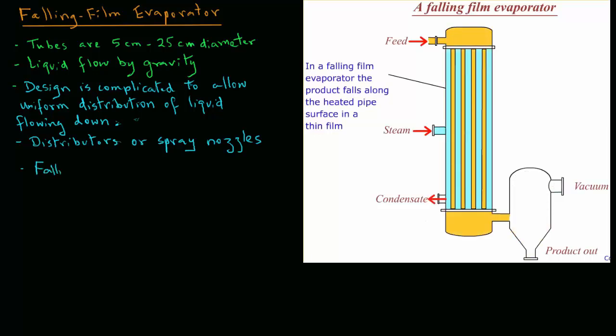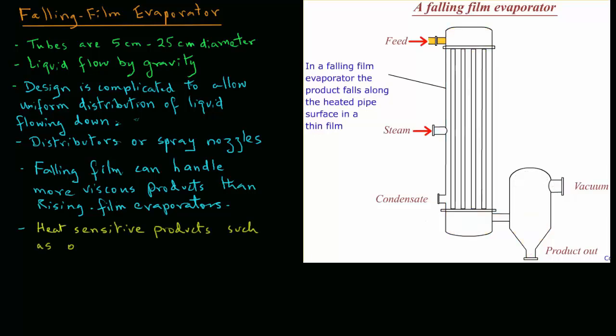The falling film evaporators can handle more viscous products than the rising film evaporators because here the flow is mainly by gravity. Typically, heat sensitive products such as orange juice concentration is done in these types of evaporators.